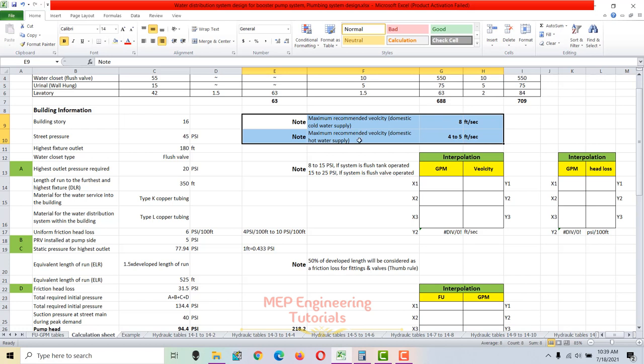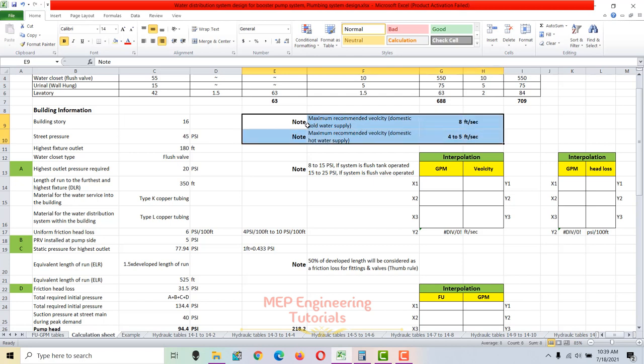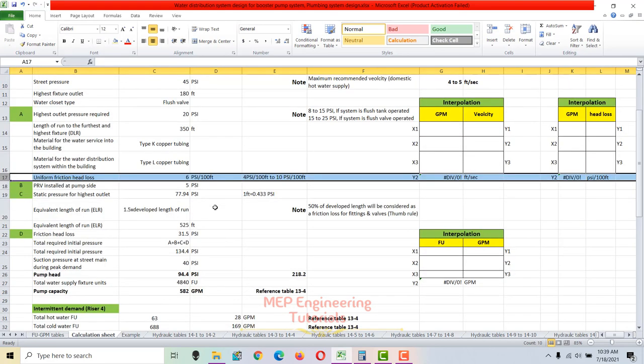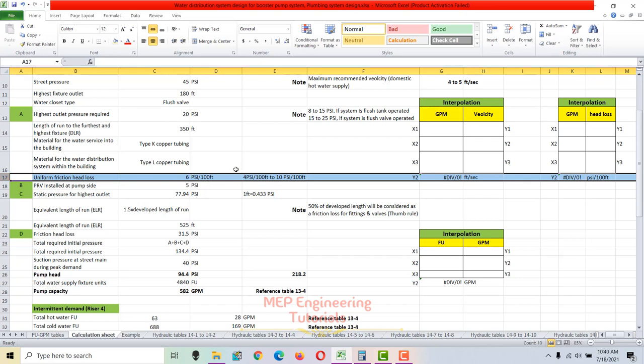If you design at higher velocities than recommended, you will have problems with noise, water hammer, and cavitation. That's why we follow these velocity limits. For the uniform friction head loss, we normally use 4 to 10 psi per 100 feet. We've used 6 psi per 100 feet here, which is the most economical design value.